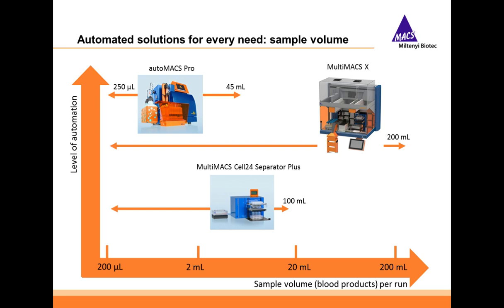Moving on to a different comparison — sample volume rather than throughput. Starting on the left with 200 microliters, moving up to 200 milliliters on the right: the AutoMACS Pro can separate from 250 microliters to 45 milliliters of blood products. The MultiMACS product family can be used for small volumes, but because we have the column block and parallel cell separation, we can go to much higher volumes. The MultiMACS Cell 24 Separator goes up to about 100 milliliters, and the MultiMACS X with fully automated cell processing can handle 200 milliliters with minimal hands-on work.